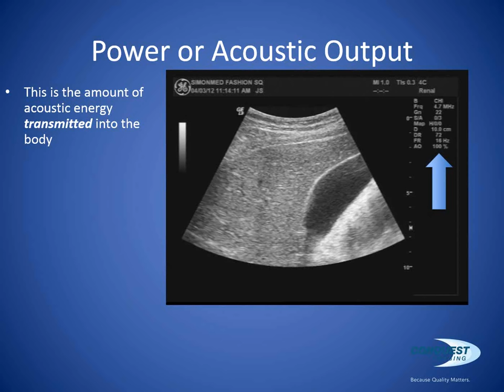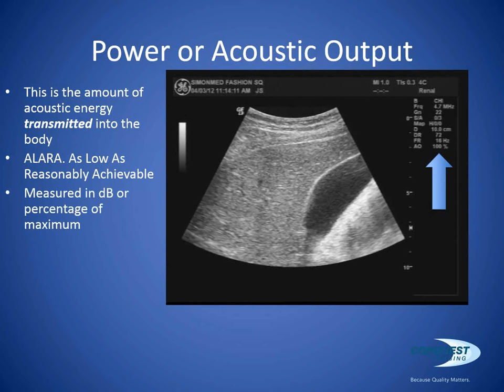Let's talk about power or acoustical output. One of the settings on an ultrasound system is power or acoustical output. You can see where I have the arrow pointed. This system here is actually a GE Logiq 9. What you're looking at in this image is my gallbladder, and you can see where it says AO and 100%. So I have the system turned up to 100% acoustical output. This is the amount of acoustic energy transmitted, and this is a key word, transmitted into the body. This is how much energy you are putting into the body. Like most imaging modalities, we want to use the ALARA principle, as low as reasonably achievable. For obstetrical work, you typically would not go with 100% output. You would reduce that down. It's typically measured in decibels or percentage of maximum output.